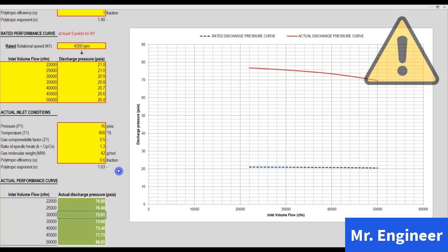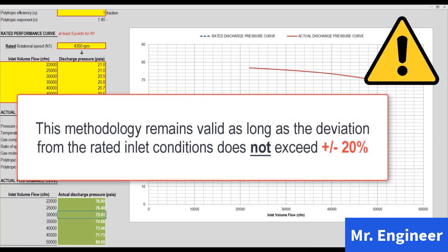Keep in mind, however, that this methodology will remain valid as long as the deviation from rated inlet conditions does not exceed plus or minus 20%. In other words, to put it simply, if your rated inlet pressure is, let's say, 100 psi, then this methodology remains valid and will yield accurate results as long as your actual inlet pressure falls between 80 and 120 psi.